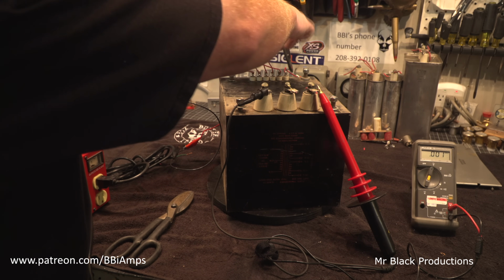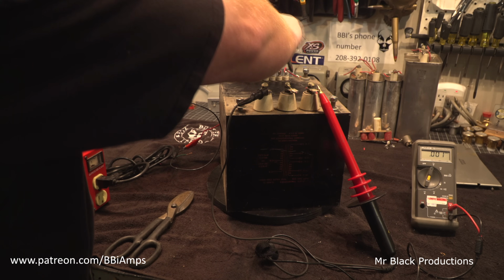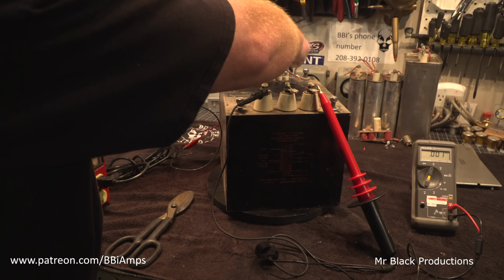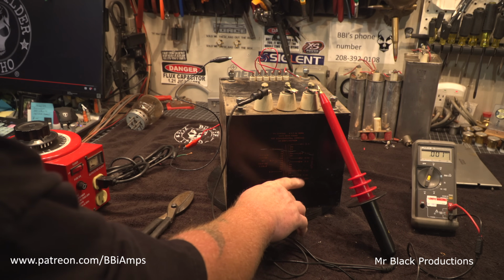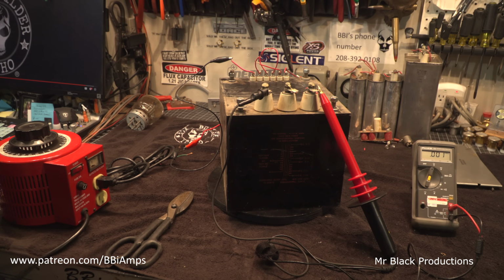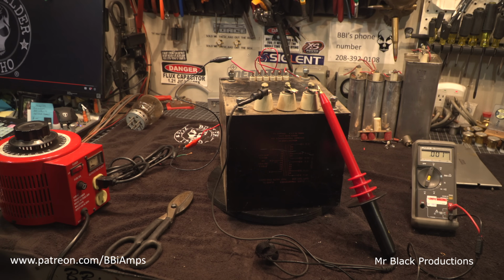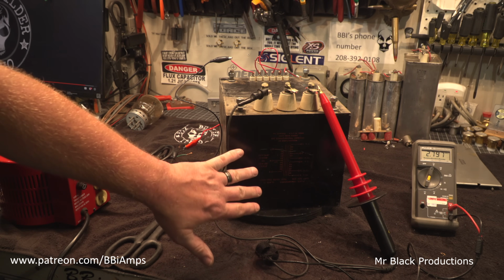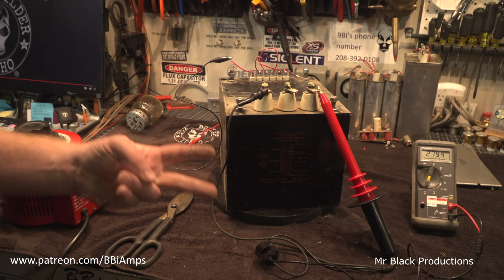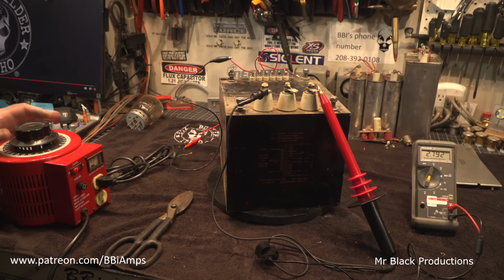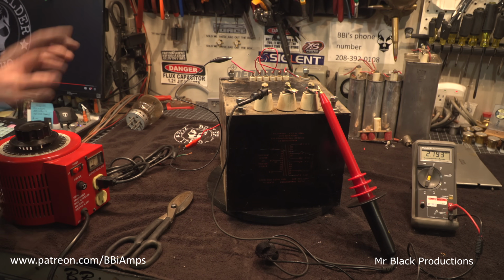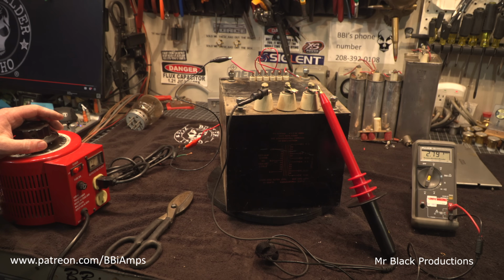Now we're going to go for the low tap. This is the 100, and we are seriesing the two 141 volt taps, so now we're going to get a lot lower voltage. Okay, oh yeah, so now we're down, you see the difference now? So by taking this winding and this winding together on 110, and we're putting in 110 volts, and all we did was change the tap on the primary side, that's a dramatic difference in voltage.